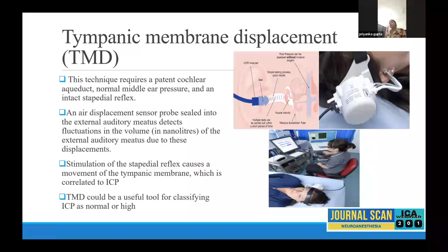And there should be an intact stapedial reflex, because it is because of that reflex that the tympanic membrane will move. So an air displacement sensor probe seals the external auditory meatus. It detects fluctuations in the volume, in nanoliters, of the external auditory meatus. Stimulation of the stapedial reflex causes a movement of the tympanic membrane, which is correlated to the ICP. But they will only say the ICP is normal or high. They will not give the exact value.